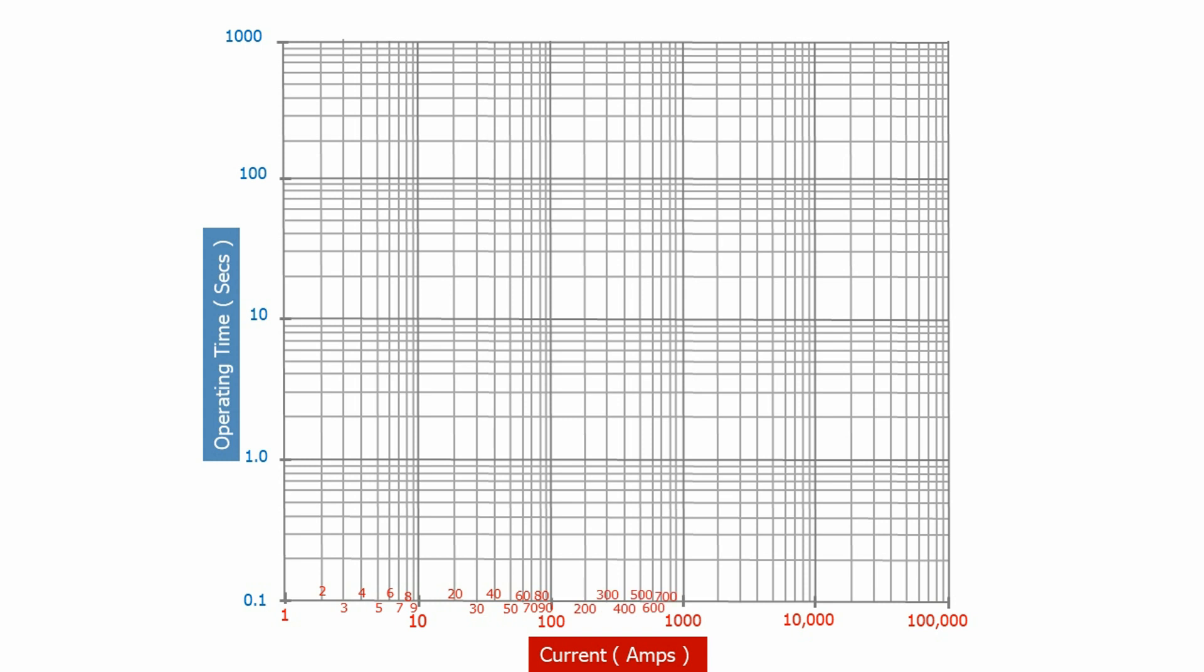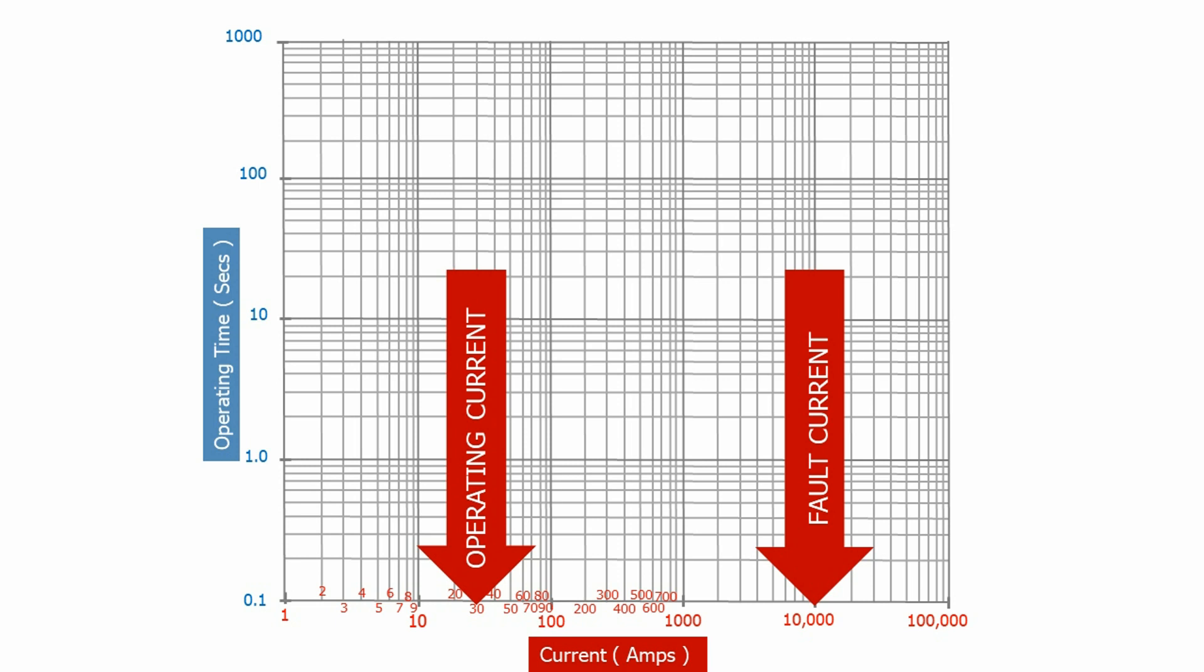Why do we use the logarithmic graph? Well, the current that we want to study has a huge range. The normal operating current for a 60 amp circuit may be 10, 20 or 30 amps, but when we get a fault the current magnitude can increase to 10,000 amps and we want to see this full range of current on the same graph. The only way we can do this is to use a logarithmic scale.